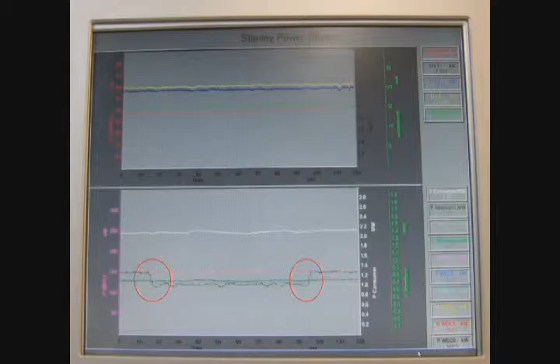This is wind energy converter number 6. A lot of information here, but in this window you can see power available is 330 kilowatts, power actual is about 148. Our excitation current is over 200 amps, and the blade angle is 18 degrees. This is how we control the turbine: you set a target number and it will vary the excitation current and the pitch angle of the blade in order to achieve that number.